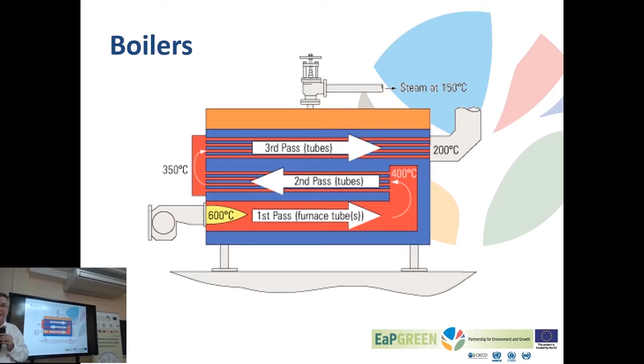In steam boilers, an issue might be return of the condensate. Condensate is hot water, 100 degrees hot water. If we dump it, we dump all the energy it takes to heat the water to these 100 degrees. So condensate should be returned to the boiler as feed water. These are, in a nutshell, the most important points to look at. Now, a few observations, a few examples to look at or to memorize when looking for optimization potential.